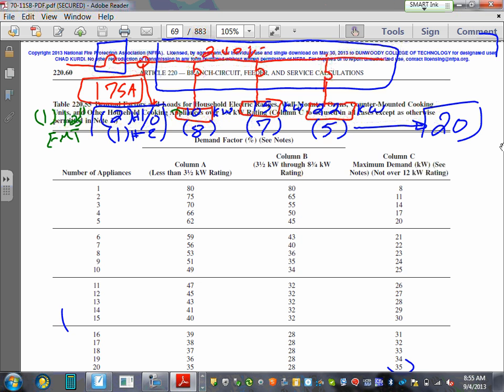Cool. All right, now we size the feeder for the system. Now they're going to come up to you and say, well, what size branch circuit do I need for these babies, right? Okay, let's go size it. For branch circuits, I'm going to start with the first one, number 10. 10 kW branch circuit. Cool. We're going to size the 10 kW branch circuit. All of them are ranges.